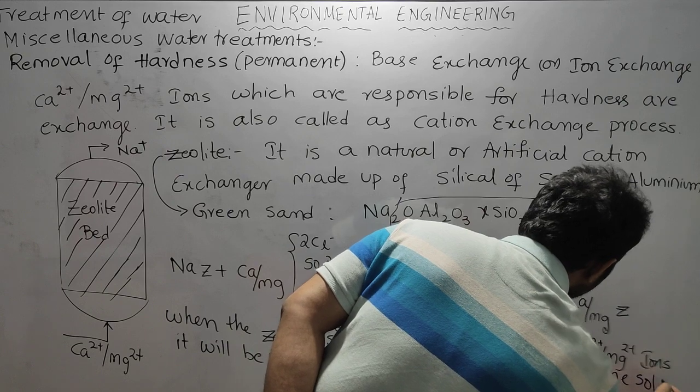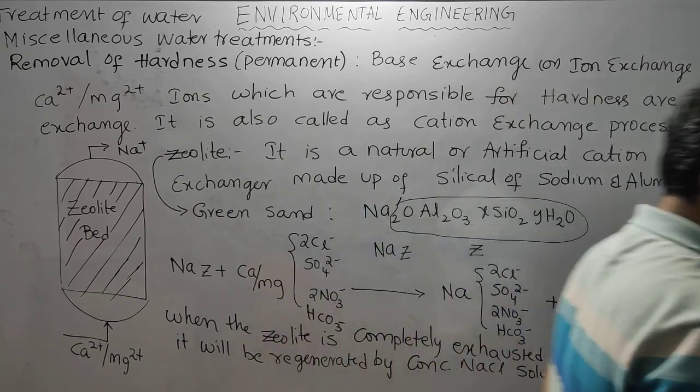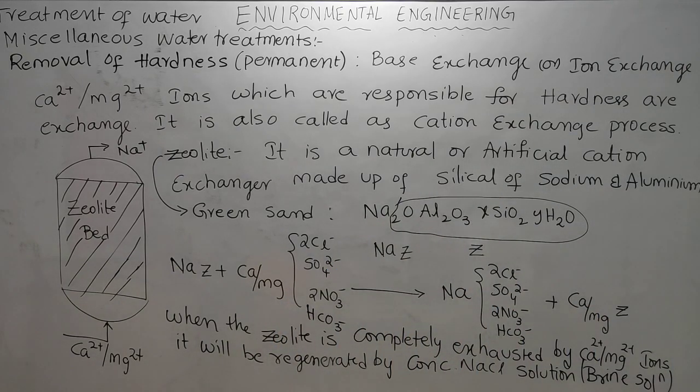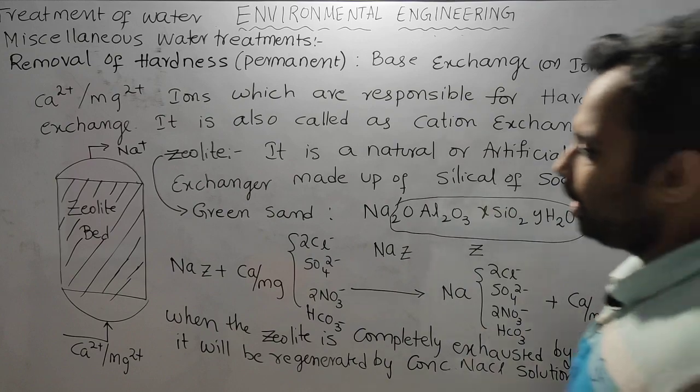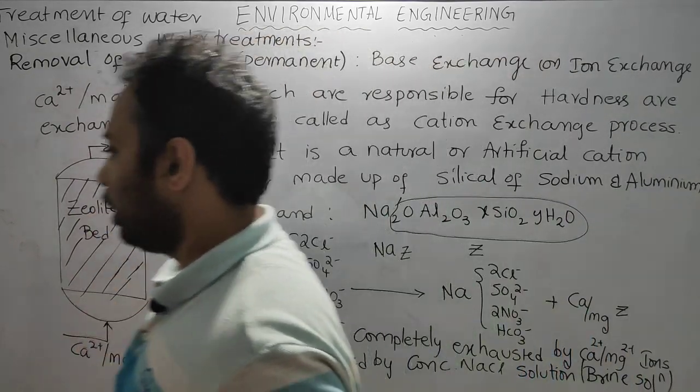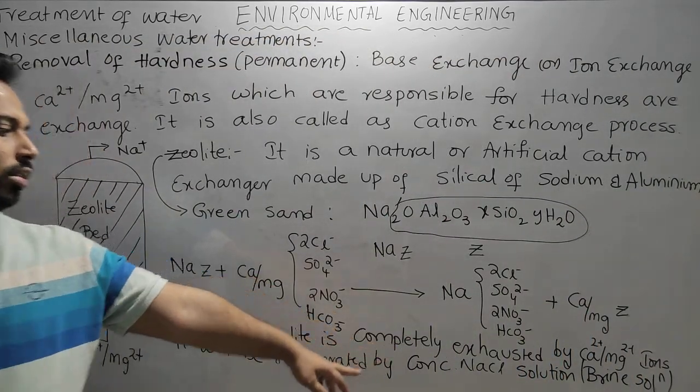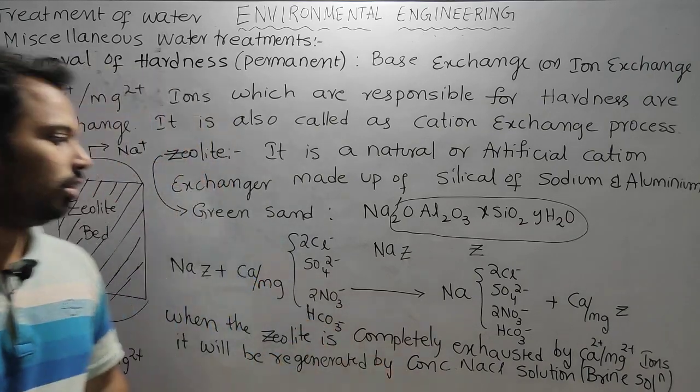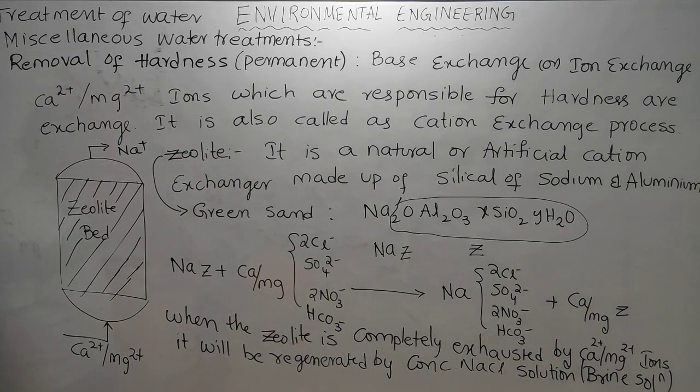So this brine solution we will use to regenerate the zeolite bed. Again, we will refill the zeolite bed with sodium ions by sending concentrated salt solution.